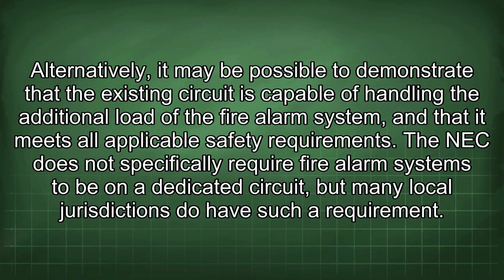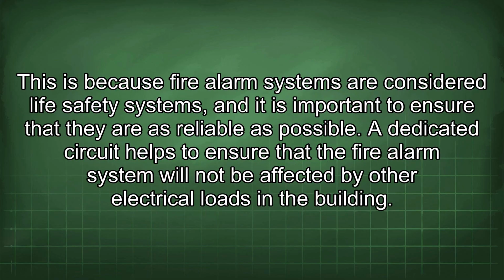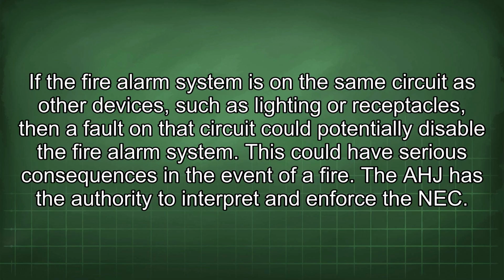The NEC does not specifically require fire alarm systems to be on a dedicated circuit, but many local jurisdictions do have such a requirement. This is because fire alarm systems are considered life safety systems, and it is important to ensure that they are as reliable as possible. A dedicated circuit helps to ensure that the fire alarm system will not be affected by other electrical loads in the building. If the fire alarm system is on the same circuit as other devices, such as lighting or receptacles, then a fault on that circuit could potentially disable the fire alarm system. This could have serious consequences in the event of a fire.